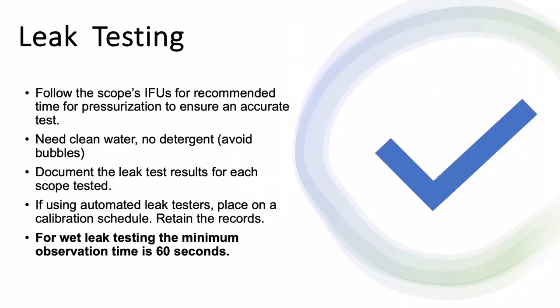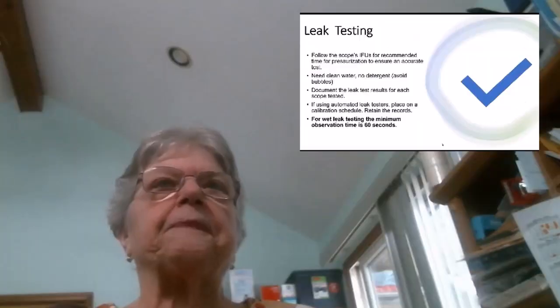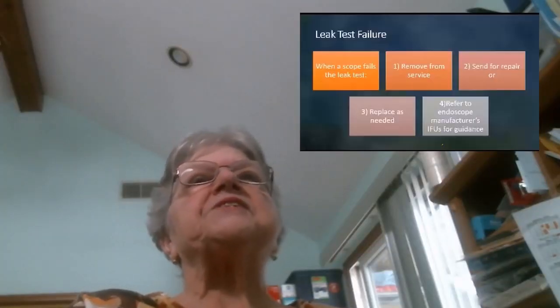Document the leak test results for every scope tested and keep those records. If you're using an automated leak tester, place it on a calibration schedule and retain those records. And if you are performing wet leak testing, the minimum observation time is 60 seconds, and I don't see that happening. What happens when a leak test fails?